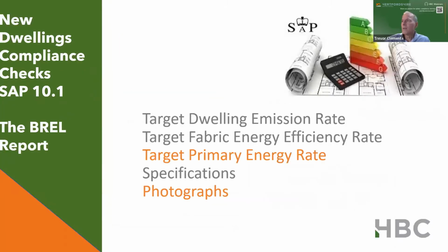Right, so for new dwellings, when we used to ask for calculations showing fabric efficiency and carbon emissions only, we're now looking at this total energy performance. So we'll be looking for the target CO2 emission rate, the TER, as we always have done, the target fabric energy efficiency rate, the TFEE. That's still there. There was a proposal to remove it in the earlier consultation, but there was pressure from responding individuals to keep that in, so it's retained.